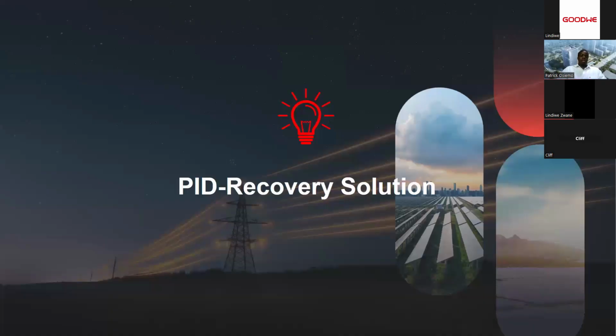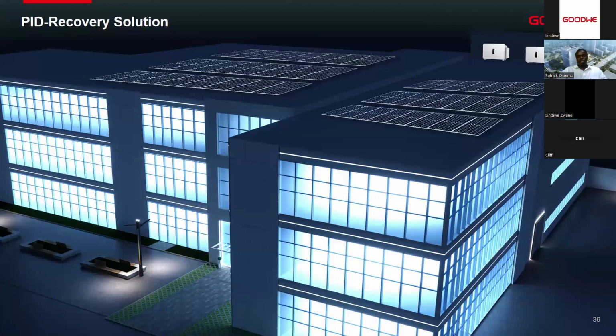Now, moving on to the PID recovery solutions, this affects the PV modules. Most of the time when PV panels are installed in very humid conditions, there's a high chance of electrons escaping to the frames of the PV panels. Over time, the PV panel generation capacity reduces, and this negatively impacts your generation capacity. Your performance ratio will also reduce.